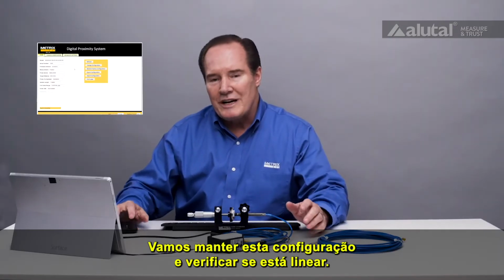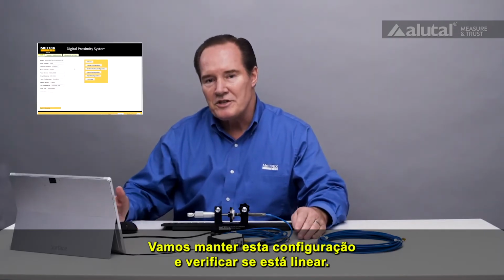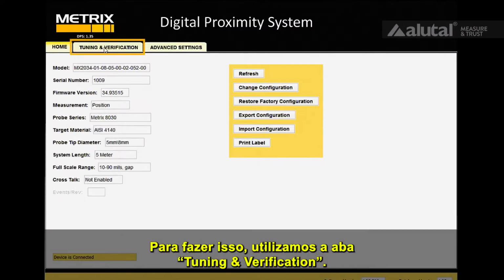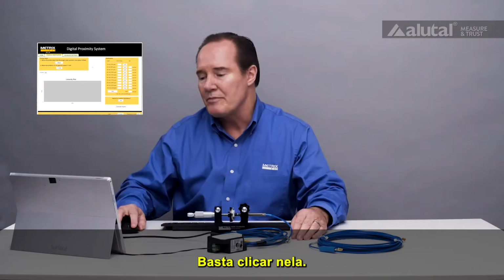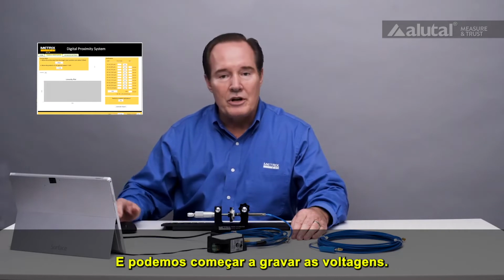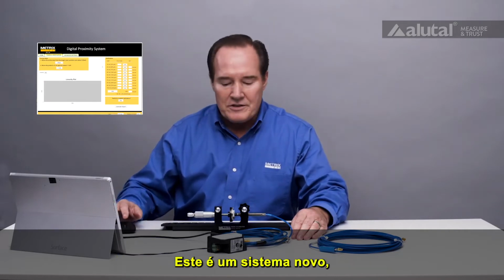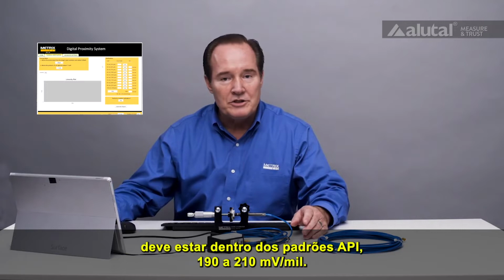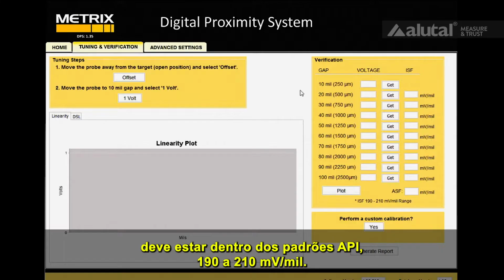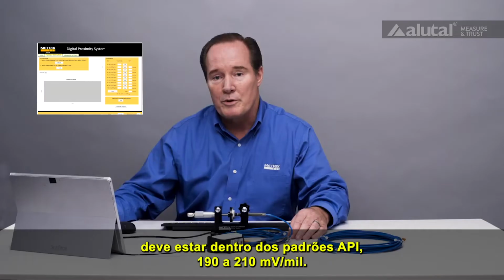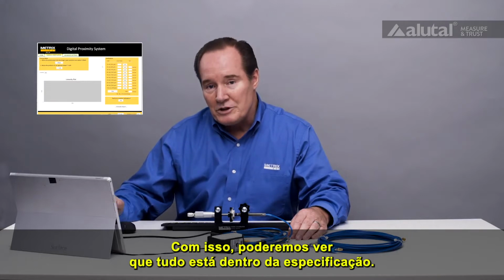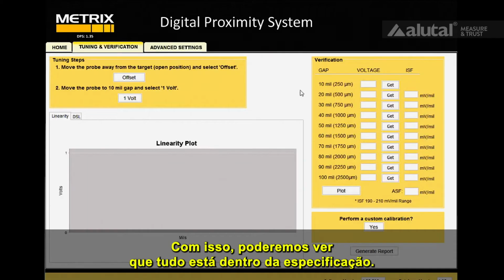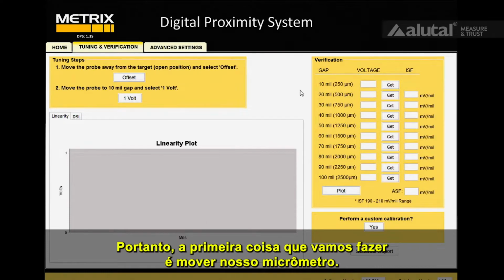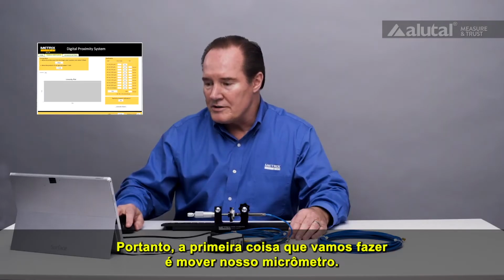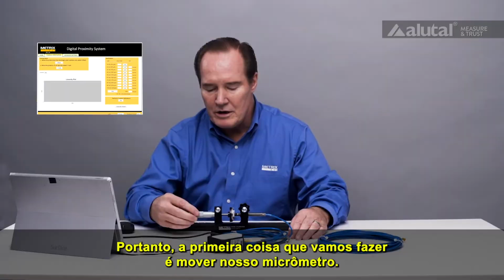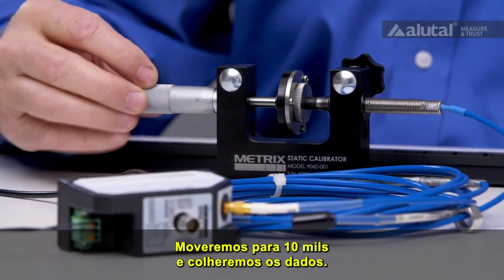So what we want to do is we're going to keep this configuration, and let's just see if it's linear. Well, to do that, we use the tuning and verification tab. You just click on that, and we can start recording voltages. And this is a system right out of the box. It should be well within the API standards, 190 to 210 millivolts per mil. And with that, we should be able to see that everything is within specification. So the first thing we're going to do is go ahead and move our micrometer. Well, we'll move it 10 mils and we'll take data.